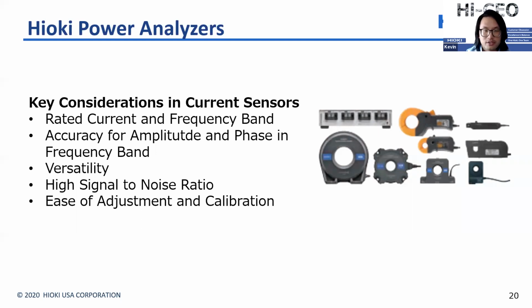Most high precision current sensors are only defined for DC current and commercial frequencies, and the phase accuracy is rarely defined. Since our sensors are voltage output, it's possible for us to define the entire measurement band. Versatility is also important. Current sensors that use the voltage output can be used in other applications, since it's easy to plug them into other instruments such as multimeters, oscilloscopes, or even recorders. When choosing a current sensor, you should also be aware that you should have a high signal to noise ratio. They should also be easy to adjust and calibrate, and typically the voltage output sensors are easier to adjust and calibrate.